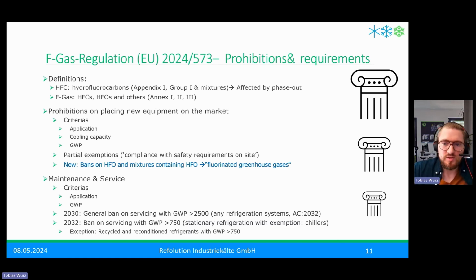The next, smaller column, the one with the most exemptions in the regulation, is the maintenance and service column. We have several criteria like the application and the GWP, but mostly it could be reduced to two timestamps where we see something happening. It's 2030, where we have this general ban on servicing with GWP above 2,500.